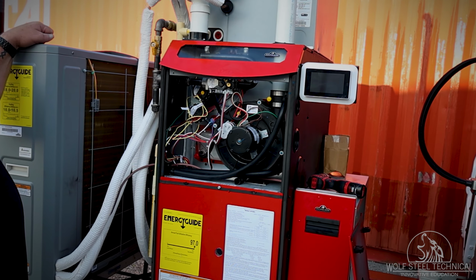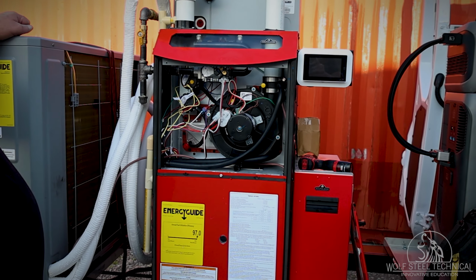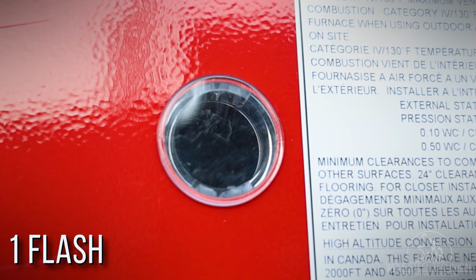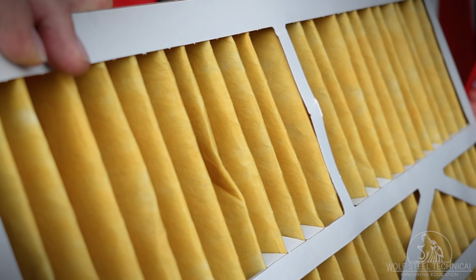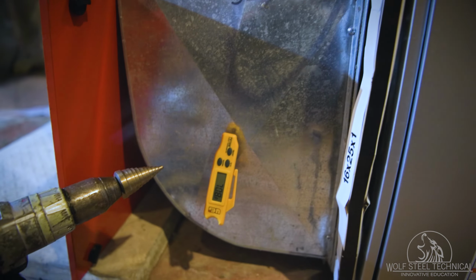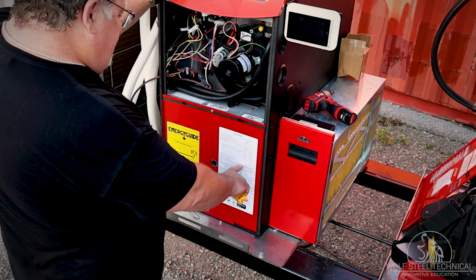Here are the solutions for the top 4 most experienced flash codes for a Napoleon furnace. A single flash signifies a high limit issue. This is normally an airflow issue, in which case the filter, coil, registers, and return air must be inspected for blockages. Next, perform a delta T check, comparing your value to the correct one on the rating plate.